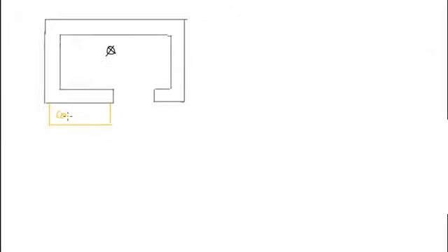So I'm going to build a little area. It's a control desk. Let's say this is where the therapists work. And they're radiation workers, remember. Here's an office. Not a great design, really, but there it is. So the goal here is to calculate the barrier thickness, so the thickness of the wall between the office or the wall between the control area. And they need to be thick enough in order to keep the exposures down below the permitted levels.